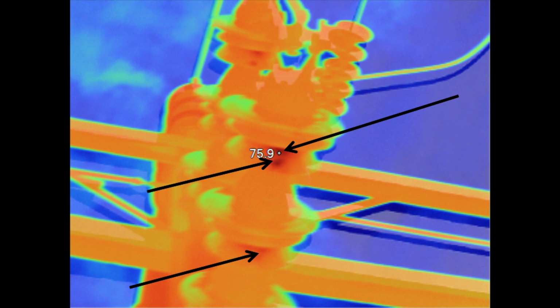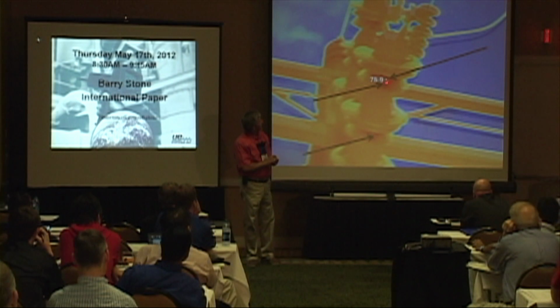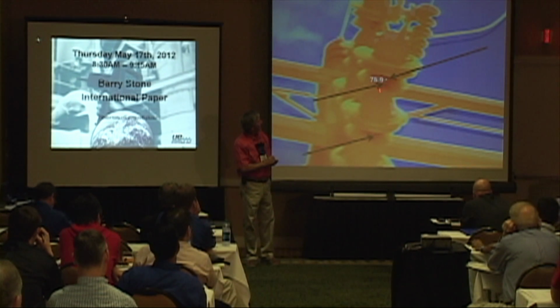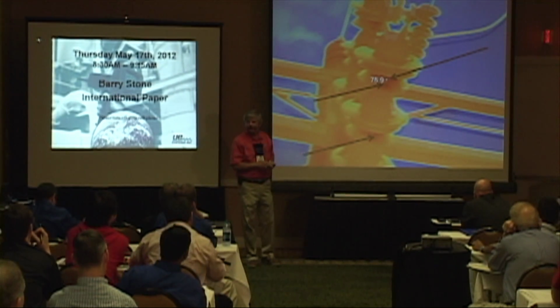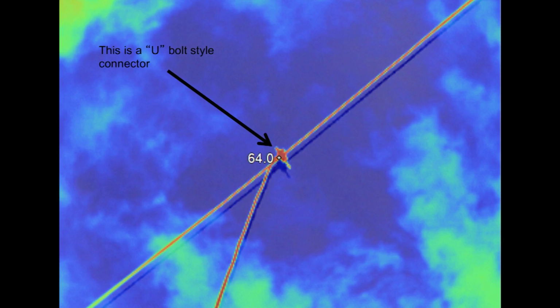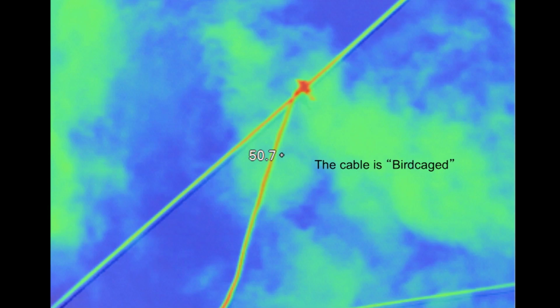Just a little closer view. If you look, right here is the same spot underneath the insulator, and here too, a U-bolt style connector. Look at the temperature difference there. Remember, I told you there was a possibility of having some kind of electrical discharge at the connection points for electricity. It's a good place to look. Look at your U-bolt connectors. You can find stuff.